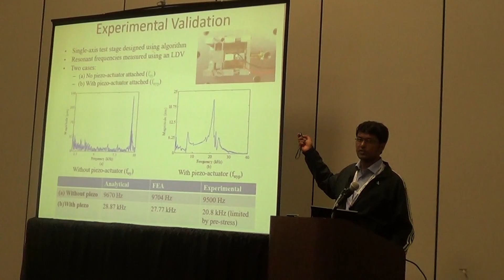And the reason for putting pre-stress is to make sure that the piezo actuator does not lose contact with the stage. So as you would have noticed, the piezo actuator is not bonded to the stage. The only way it is attached is using this stressing mechanism over here. And so there is a possibility that during motion, the piezo actuator actually loses contact with the stage over here, which is why we apply an initial pre-stress. And we find that the pre-stress required to make sure that the piezo actuator does not lose contact throughout the scan range turns out to be greater than the strength of the piezo actuator itself. Therefore, we don't apply such a large pre-stress.